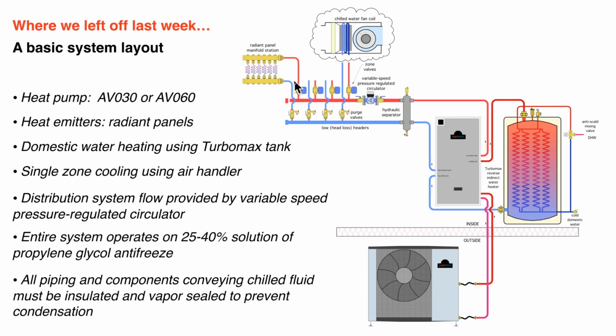I'm showing them going out, in this case, to some radiant panel manifold stations, or perhaps one of them, or more than one of them, could go to a chilled water air handler. And that air handler could also be used in heating mode. So with this part of the system, it's almost limitless what you can create using hydronics technology. The important thing is to keep the water temperatures low for good performance on that heat pump.